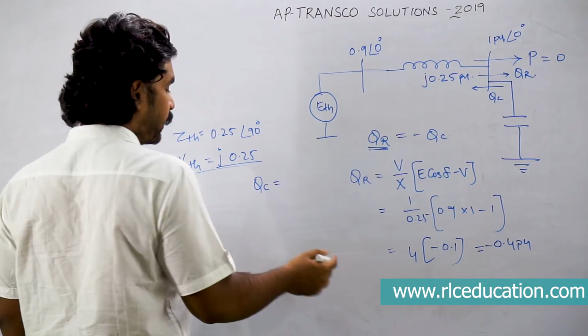If QR is minus 0.4 per unit, what is the per unit MVAR supplied by the capacitor bank? It is the minus of this, that is 0.4 per unit. Now you have the per unit capacity of the capacitor bank. If you are supposed to find the actual value, it will equal the per unit value multiplied by the base. The base given in the question is 100 MVAR.